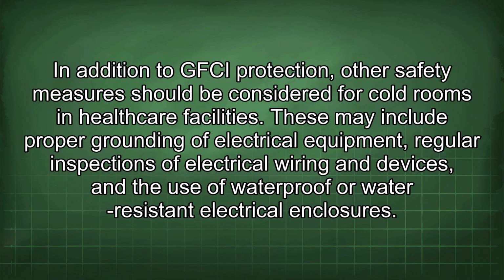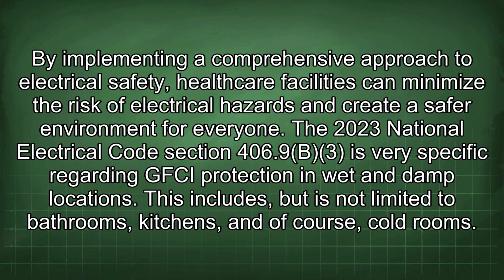In addition to GFCI protection, other safety measures should be considered for cold rooms in healthcare facilities. These may include proper grounding of electrical equipment, regular inspections of electrical wiring and devices, and the use of waterproof or water-resistant electrical enclosures. By implementing a comprehensive approach to electrical safety, healthcare facilities can minimize the risk of electrical hazards and create a safer environment for everyone. The 2023 National Electrical Code Section 406.9(B)(3) is very specific regarding GFCI protection in wet and damp locations.